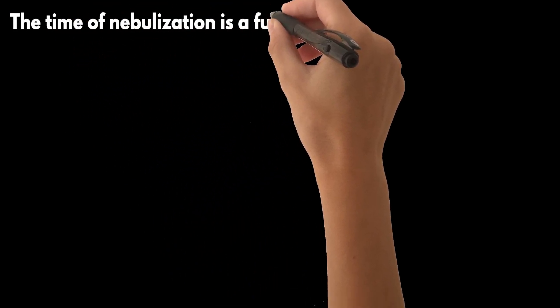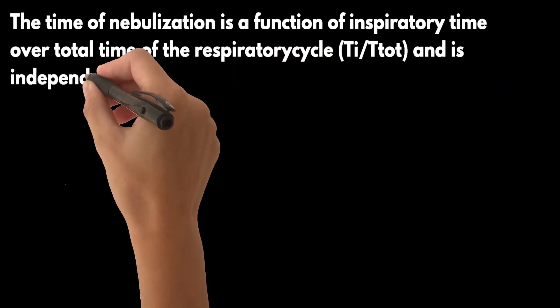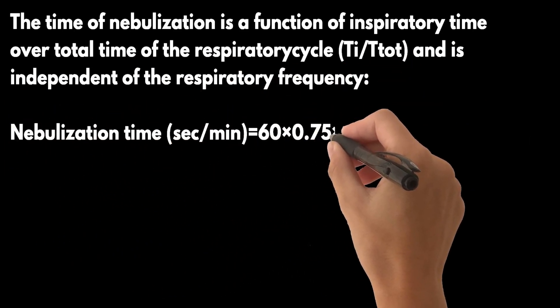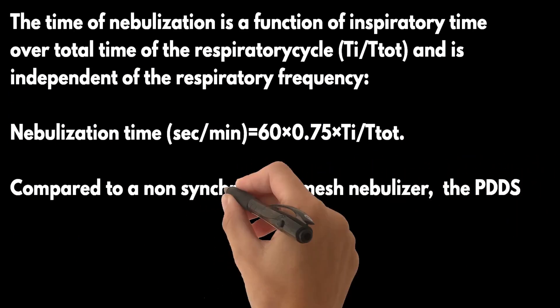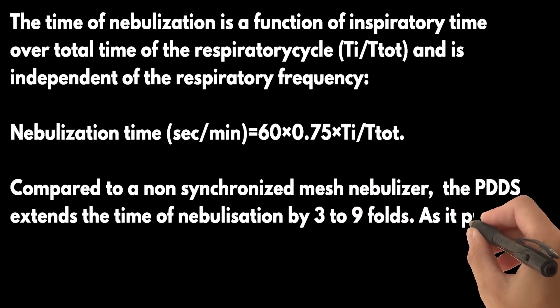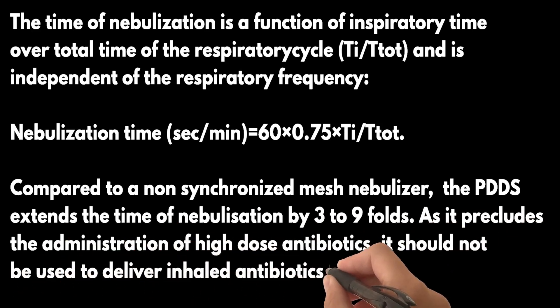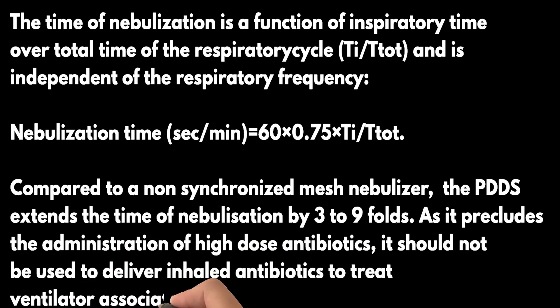The time of nebulization is a function of inspiratory time over total time of the respiratory cycle (Ti/Ttot) and is independent of respiratory frequency. Nebulization time in seconds per minute equals 60 × 0.75 × Ti/Ttot. Compared to a non-synchronized mesh nebulizer, the synchronized mesh nebulizer (PDDS) extends the time of nebulization by three to nine folds. As it precludes the administration of high-dose antibiotics, it should not be used to deliver inhaled antibiotics to treat ventilator-associated pneumonia.